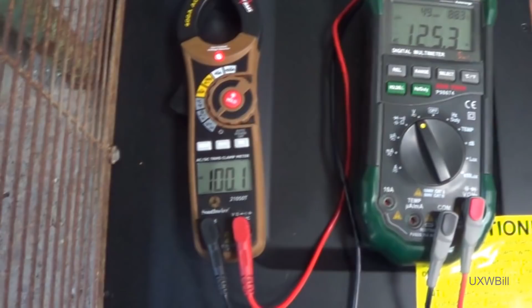Here again I've hauled the two meters out to demonstrate the voltage adjustment capability of this UPS. This is connected to the line power provided by the building and the power grid, and the clamp meter is attached to the output of the UPS. So too is the box fan, so we'll just go ahead and have a little run up here.